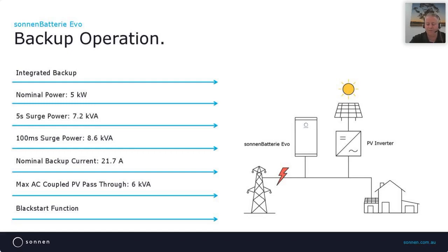The sonnenBatterie Evo also has a black start function. If there is a grid outage and the sonnenBatterie Evo still has storage capacity available, it has the ability to provide a grid reference to the AC coupled PV inverter, creating its own microgrid, allowing the backup circuits to continue to be supplied by PV if it is available, and to also recharge the battery system for use when the PV stops producing.